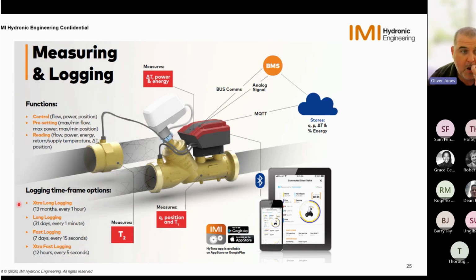So as you can see, on an extra long log, this is keeping 13 months of data. So every hour of the day, it's logging for a whole 13-month period, and that is fully retrievable from the cloud itself. Or the long log, which is doing 31 days every 1 minute. Our fast log, 7 days every 15 seconds, and then our extra fast, which is over a 12-hour period, is every 5 seconds. And you can stipulate this within the cloud, how much data you want and how much logging you would like to see.